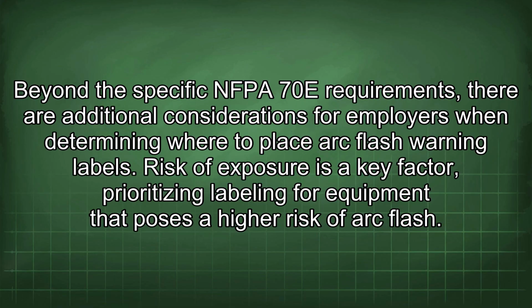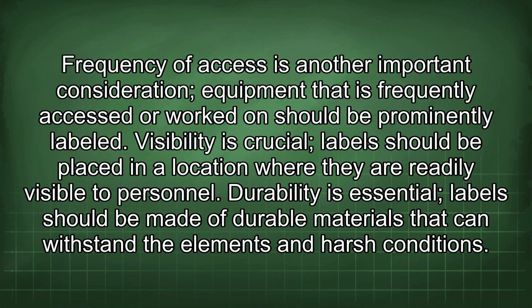Beyond the specific NFPA 70E requirements, there are additional considerations for employers when determining where to place arc flash warning labels. Risk of exposure is a key factor, prioritizing labeling for equipment that poses a high risk of arc flash. Frequency of access is another important consideration. Equipment that is frequently accessed or worked on should be prominently labeled. Visibility is crucial. Labels should be placed in a location where they are readily visible to personnel. Durability is essential. Labels should be made of durable materials that can withstand the elements and harsh conditions.